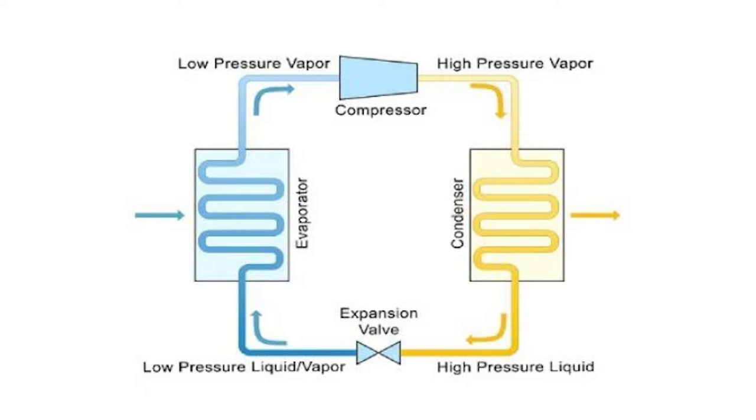The heat absorbed from the cabinet raises the refrigerant temperature above its liquid saturation point, thereby converting the low pressure liquid to a low pressure vapor, which then enters the compressor and the cycle then repeats itself. The change of state that happens inside the evaporator also happens without a change in temperature, and the heat absorbed for the process is known as the latent heat of evaporation.